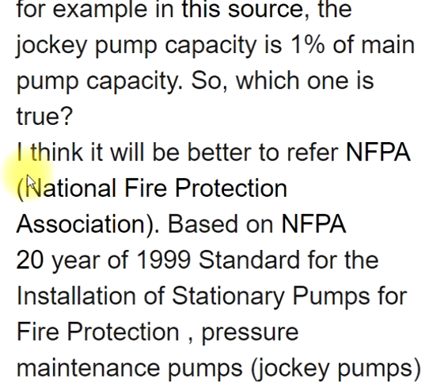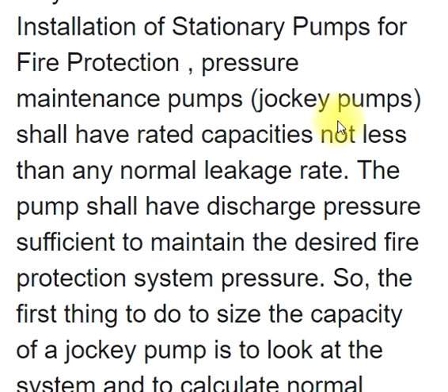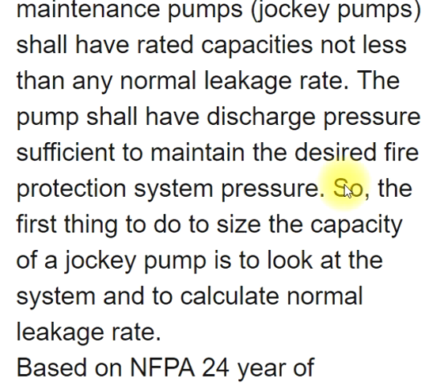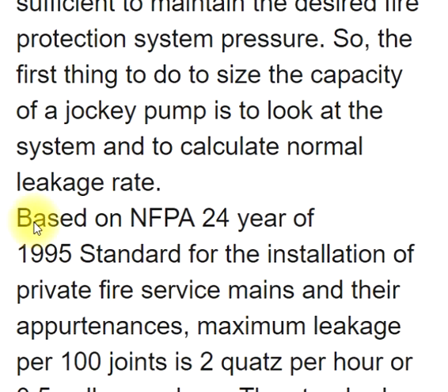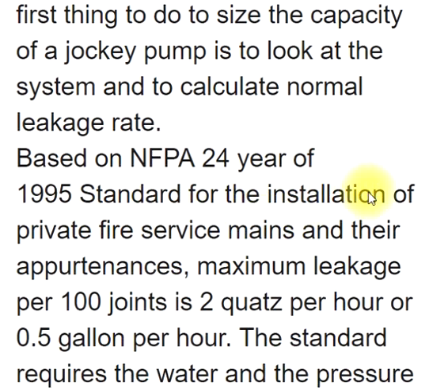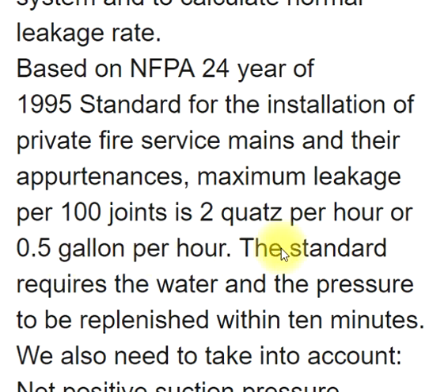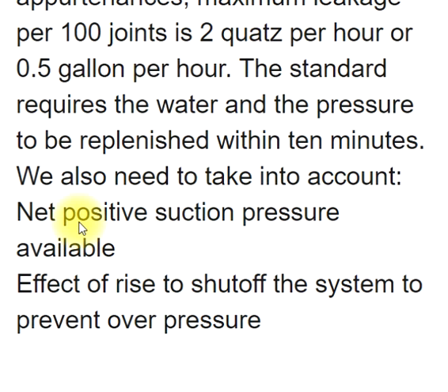Which answer is correct? It is best to refer to NFPA — the National Fire Protection Association. Based on NFPA 20 (1999 standard for the installation of stationary pumps for fire protection), pressure maintenance pumps (jockey pumps) shall have rated capacities not less than any normal leakage rate, and the pump shall have discharge pressure sufficient to maintain the desired fire protection system pressure. Therefore, the first step is to calculate the normal leakage rate. Based on NFPA 24 (1995 standard for the installation of private fire service mains and their appurtenances), maximum leakage per 100 joints is 2 quarts per hour (0.5 gallon per hour). The standard requires water and pressure to be replenished within 10 minutes. We also need to account for net positive suction pressure available, and the effect of rise to shut-off to prevent overpressure.